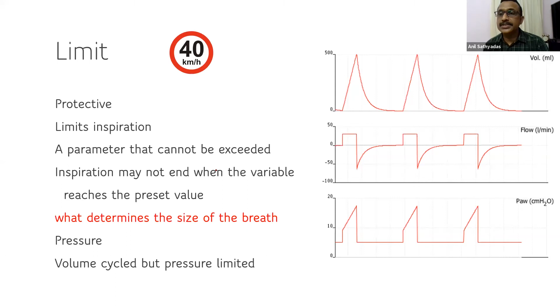So how to set the P limit? Next question. In the Maquet ventilator, you take the alarm profile, the alarm setting screen. When you take the alarm setting screen, you can see we have asked the ventilator to sound an alarm when the pressure increases to 40 centimeters of water. Whatever pressure you have kept for the high pressure alarm to sound will act as the P limit. Okay, so go to the alarm setting and see what is the pressure that you have kept for the high pressure alarm to sound. We have asked the ventilator to sound an alarm when the pressure reaches 40. That will act as a P limit. So what is the P limit here?